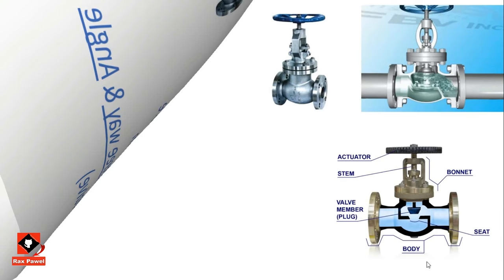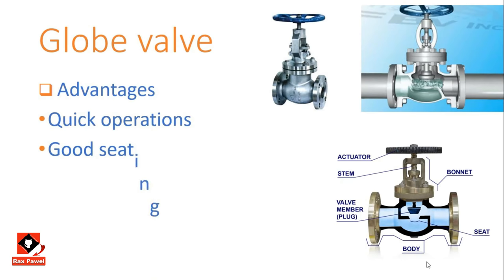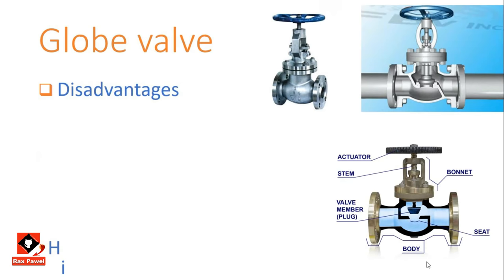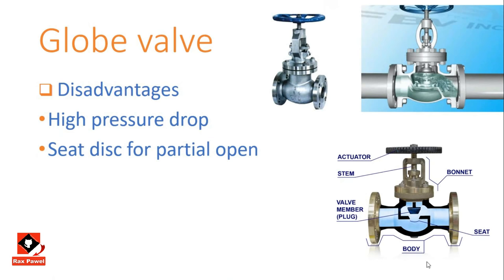Advantages of the globe valve: it can operate quickly due to its short stem, and it is the most reliable form of seating, providing positive shut-off. Disadvantages: it has a higher pressure drop than the gate valve, and the seat disc is subject to wear when partially open.